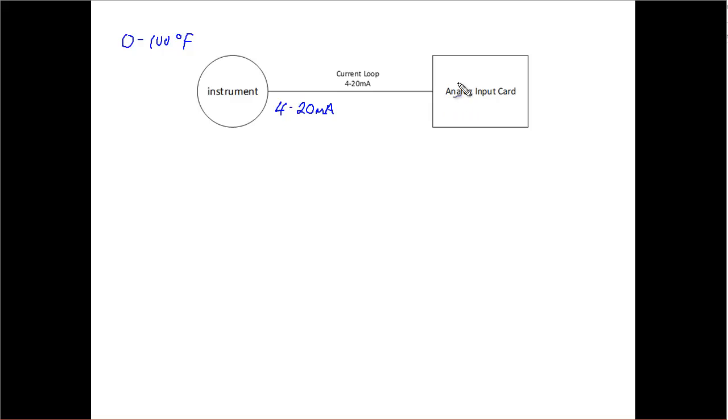The analog input card in the computer or the control device is going to convert that to a voltage that's then going to go into our A to D converter. Let's say that we're measuring 50 degrees Fahrenheit and let's say that this is a 20-bit card. It's a 20-bit analog to digital converter.